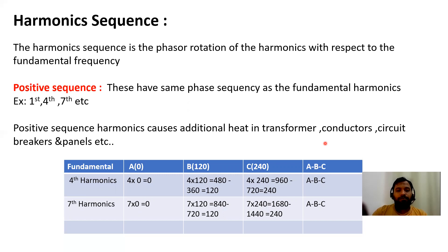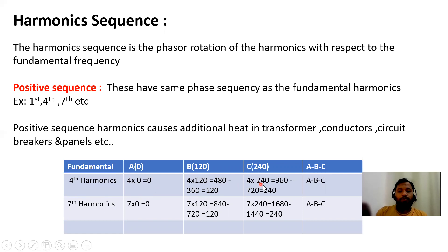Positive sequence harmonics follow the same phase sequence as the fundamental frequency. Examples are the 1st, 4th, and 7th harmonics. For the 4th harmonic: 4×0=0, 4×120=480, and 480−360=120. Then 4×240=960, and 960−720=240. So the phase rotation is 0, 120, 240 — the same as our fundamental. The 7th harmonic similarly gives 0, 120, 240. These are called positive sequence harmonics.